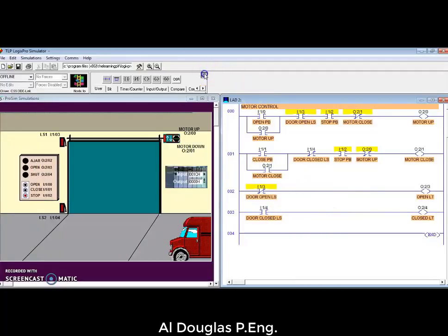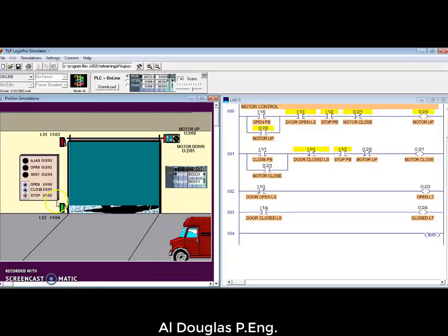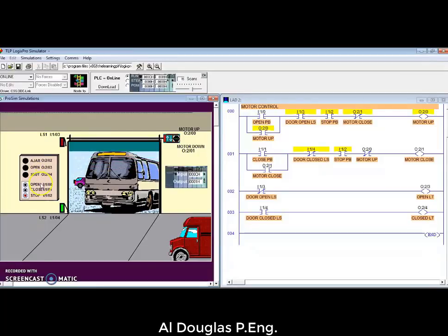And let's try these out. We'll work on the ajar one next. So right now, this is lit up. This appears to be correct. We are shut, and we are reading the shut light. Let's try opening this. Shut light goes off as we are opening. And then we should see open light come on when we actually reach the top. So these are working correctly right now. So we wrote those correctly.